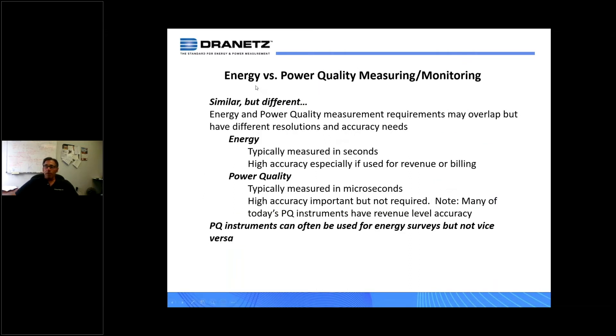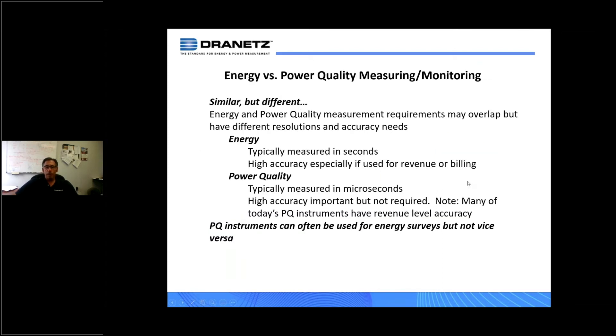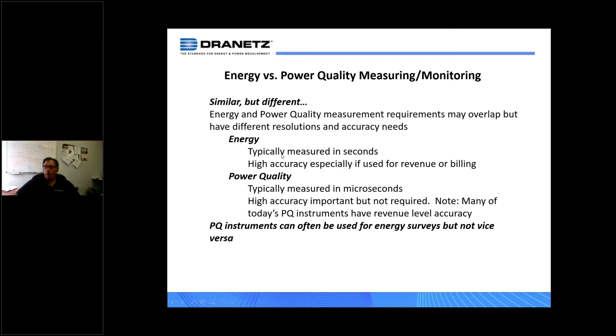What are the distinct differences between energy and power quality measuring devices? Energy and power quality measurements may overlap, but they have different resolution and accuracy needs. For energy, measurements are typically in seconds — that's usually for billing in commercial, industrial, and residential settings — and high accuracy is needed, certainly for revenue or billing purposes. This is where revenue standards come in to certify an energy meter.